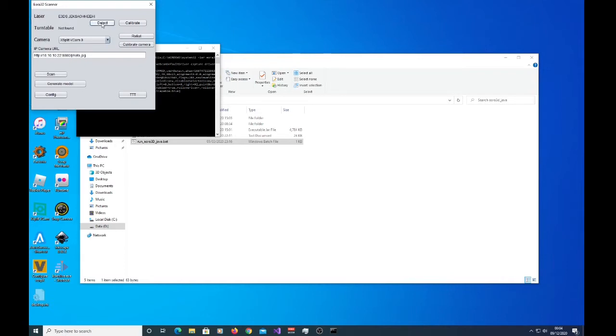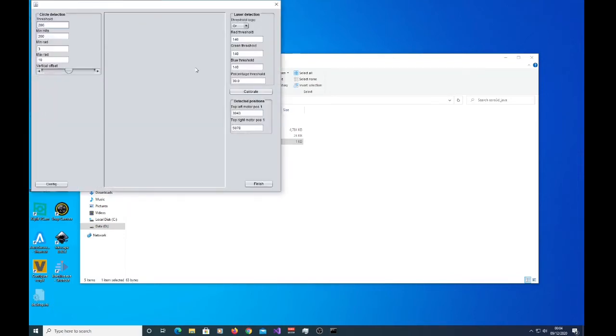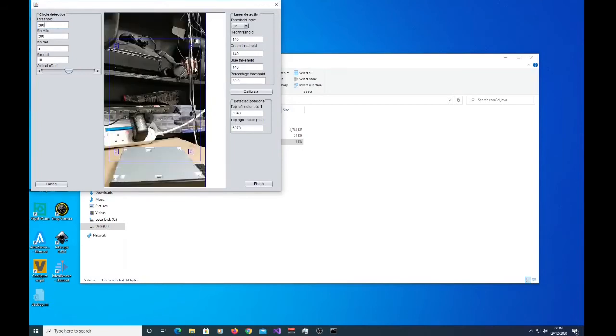Right, so it's now detected the turrets, changed colour, and it's now moving the turret back to the 0 position. So as you can see, laser serial number detected there. And what we're going to do is change the camera over to the IP camera, which is the IP camera app from the Android store. There's an equivalent one on iOS. And there we go, there's the URL for grabbing a single shot from the IP camera. Hit the calibrate button, and there we go.